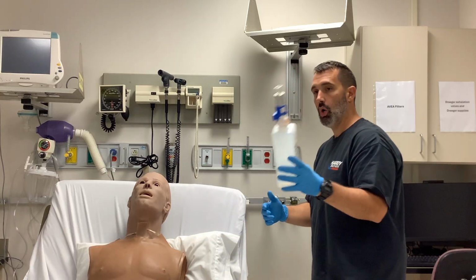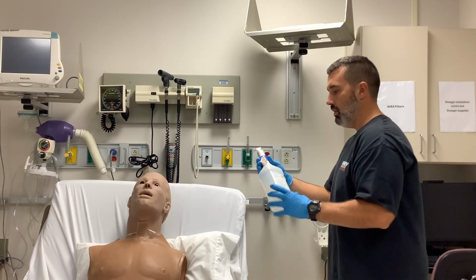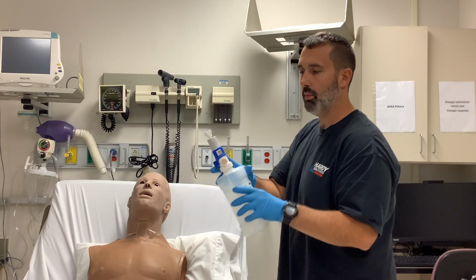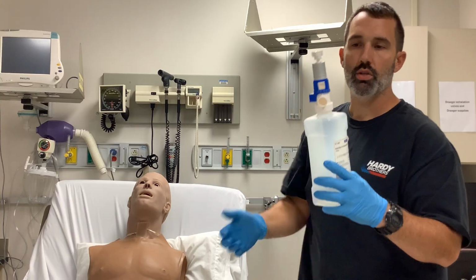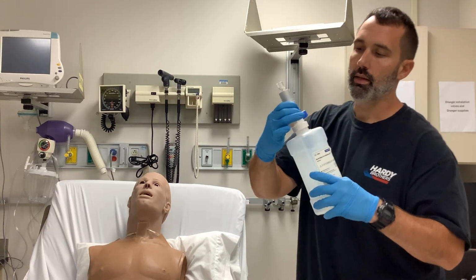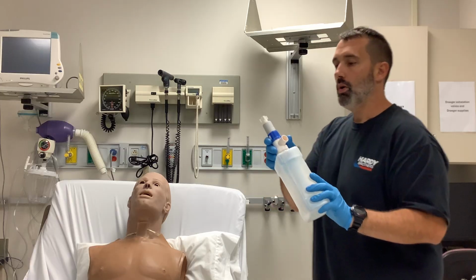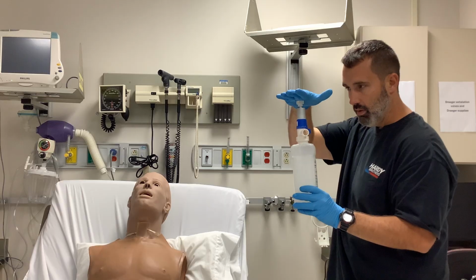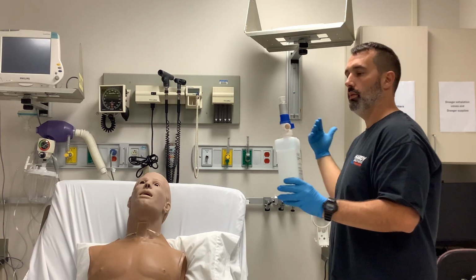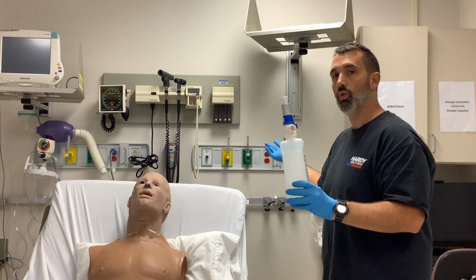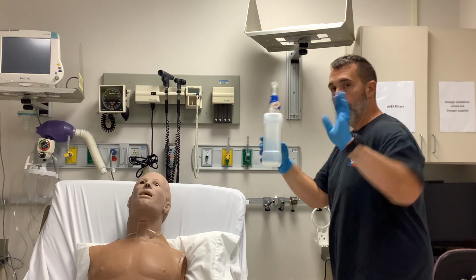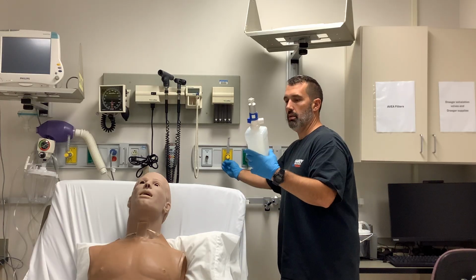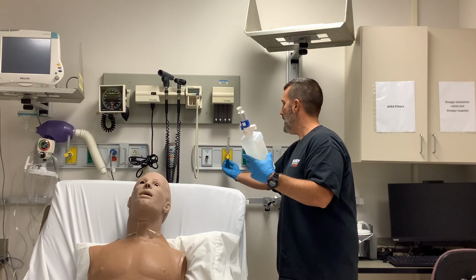So if I take a large volume nebulizer with the air entrainment collar on it, this allows me to go to 28% all the way up to 100%. Again, here you can see at 28%, window's as big as it's going to get. At 100%, that window closes. So we are dependent upon what flow meter this is attached to, and what the flow setting that we have for the overall total output flow.